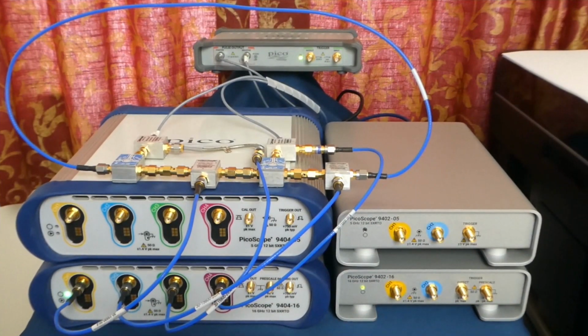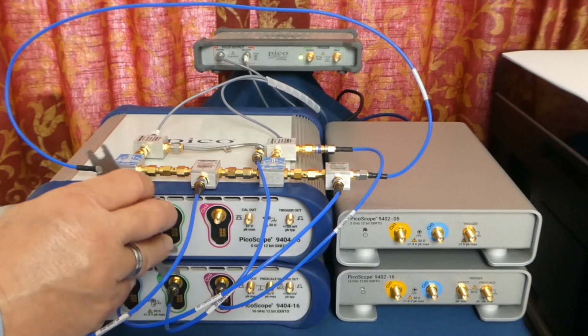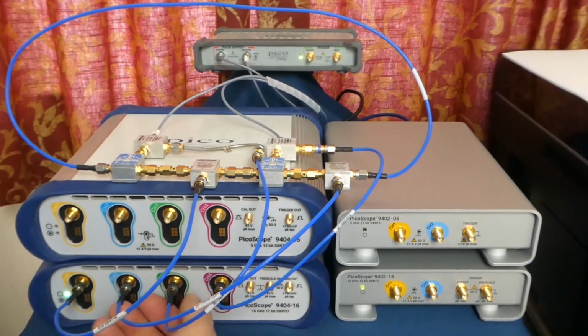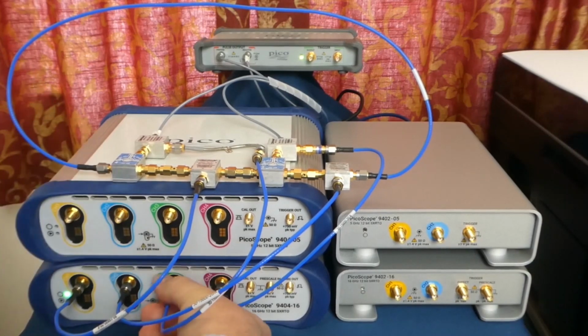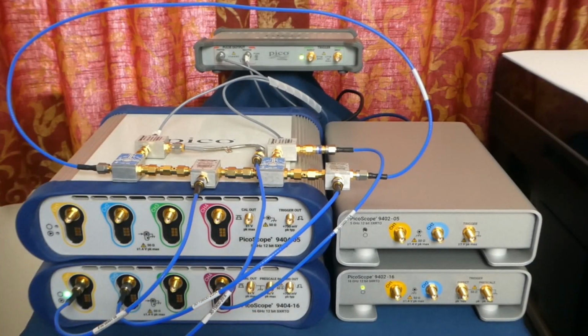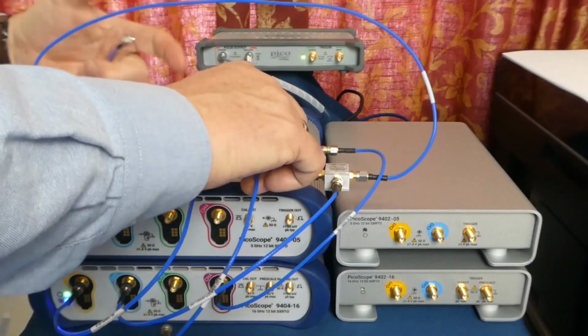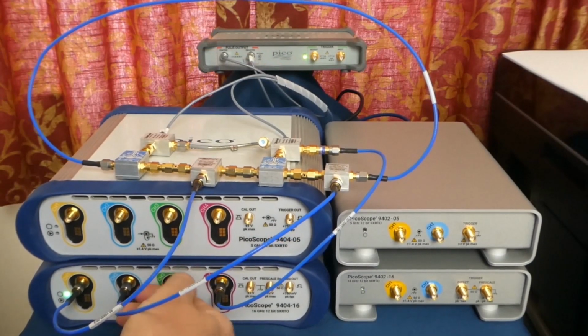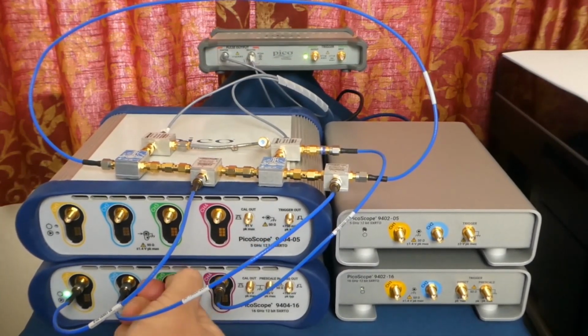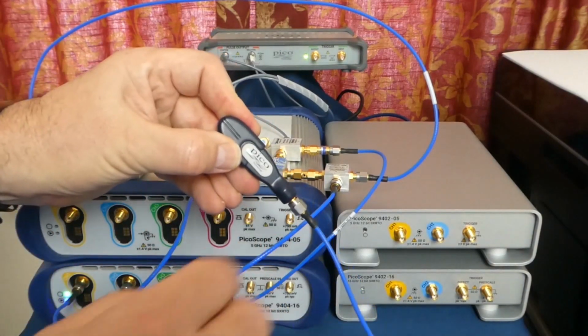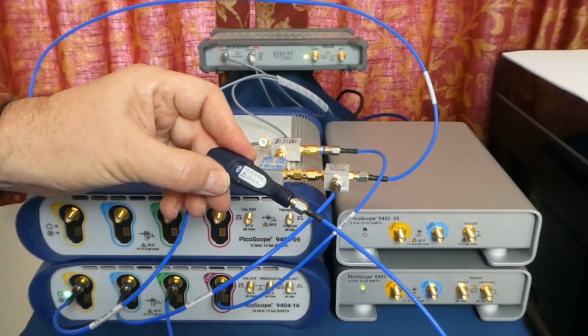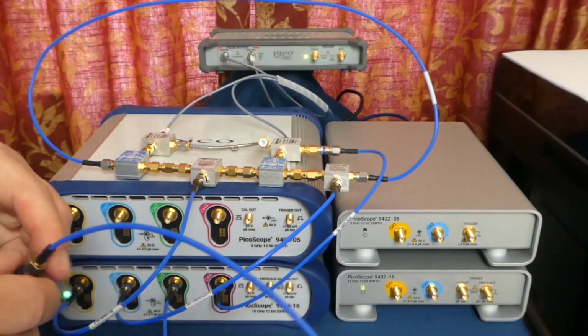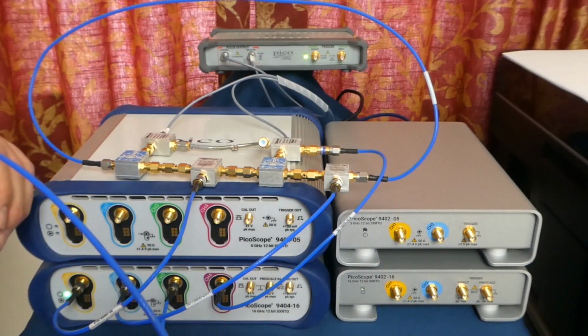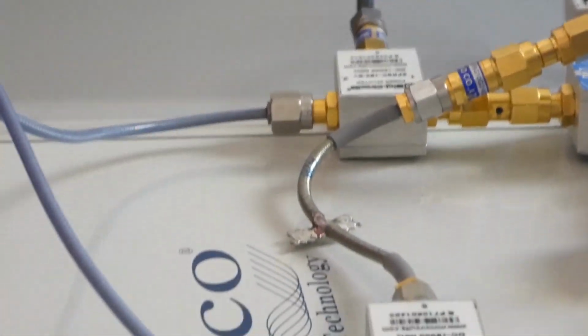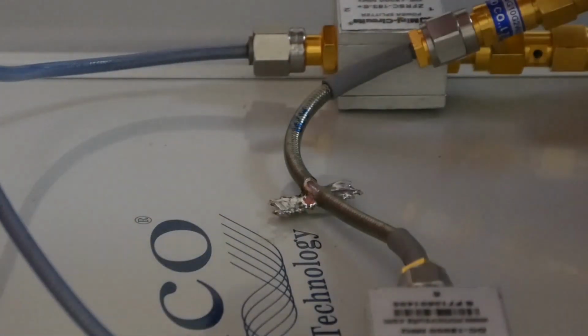While we're here, let's demonstrate the PicoConnect probes. Let's take this connection off here using my very handy Pico wrench. Absolutely ideal for all RF engineers, that. Had to design one, couldn't buy one. Let's put the probe in instead. This is our PicoConnect 9 gigahertz probe, DC coupled. And then we need to probe this terminated line as carefully as we can. Let's see if we can get a connection to that.